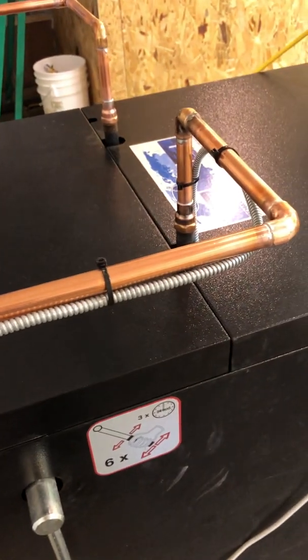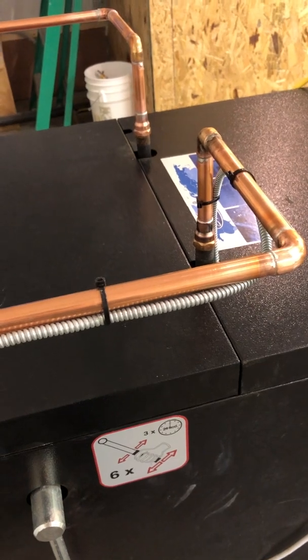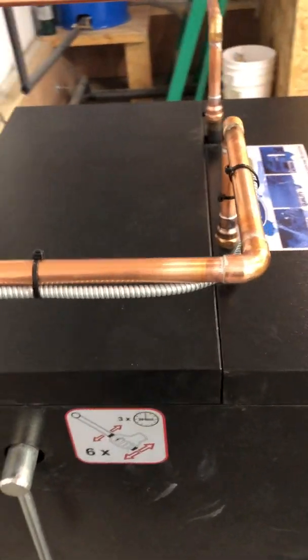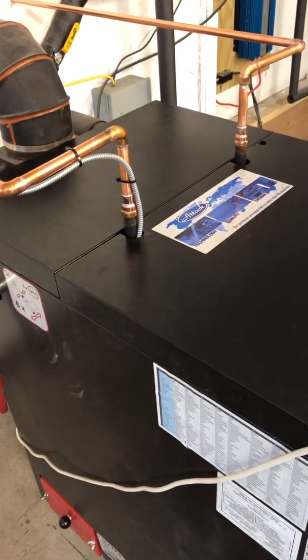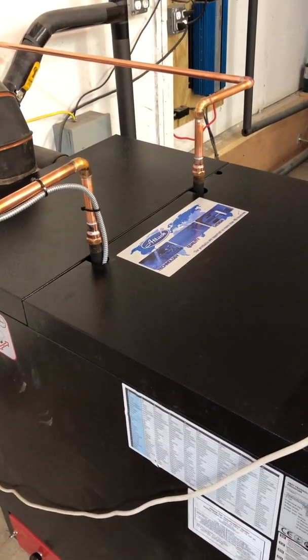So between the battery backup and this protection valve, we've pretty much covered all the instances where power failure or circulator pump failure could cause an overheat situation and possible damage to your boiler, if you don't have these protection measures installed.